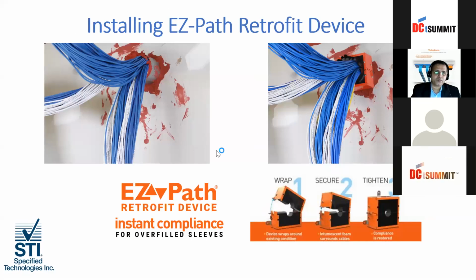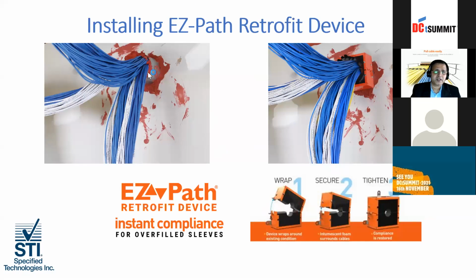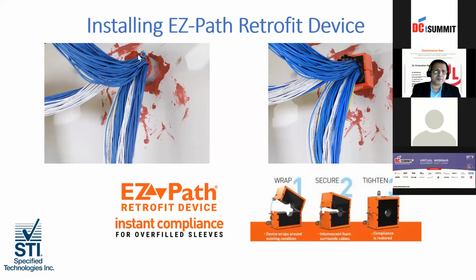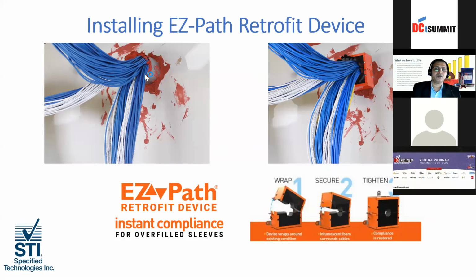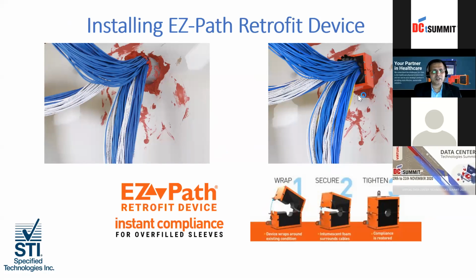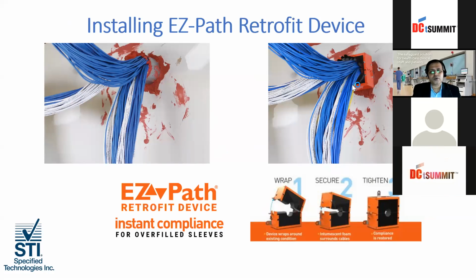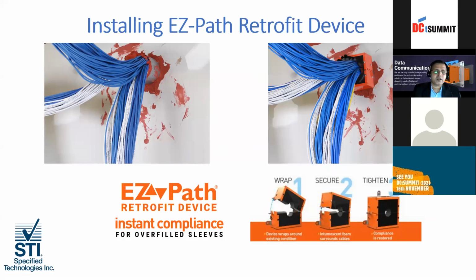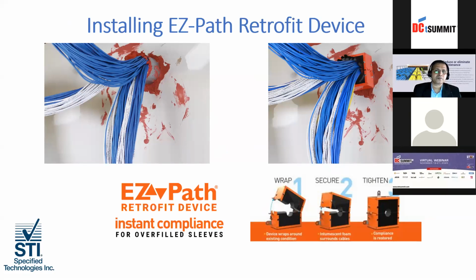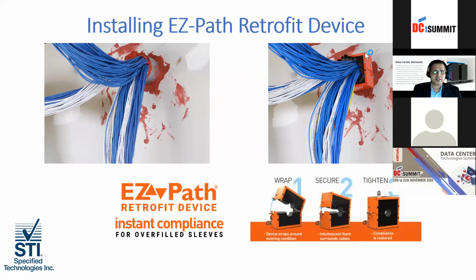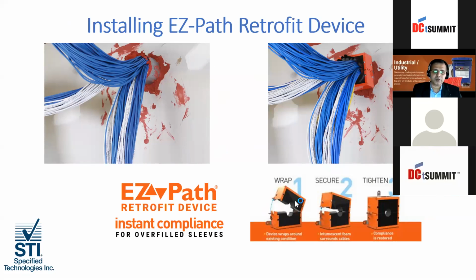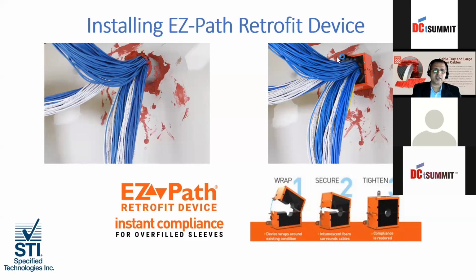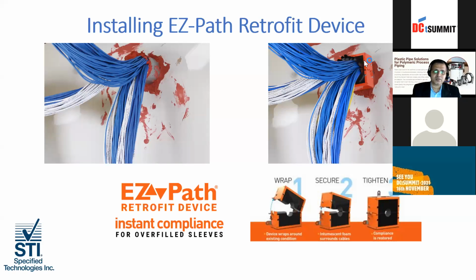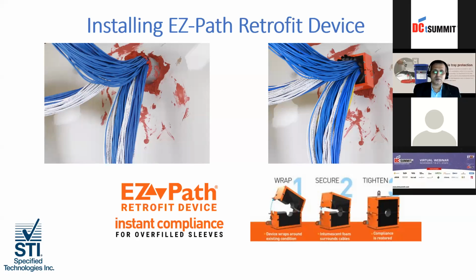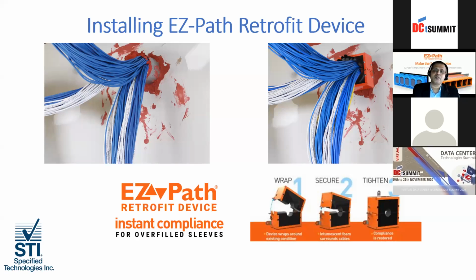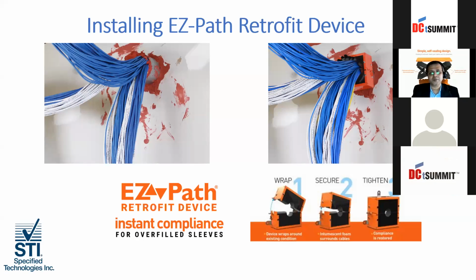This is an overfilled scenario, which you can see towards your left-hand side. The cables are 100% filled up, and the sealant is just applied for namesake. We have a retrofit device which is very easy to install, and it can support 100% filled cables, and the cables can be changed at any given point of time. The sleeve will remain as it is. The device has to be just, you can see at the right-hand side bottom, wrap, secure, tighten, that's it. And the cable can be pulled and pushed n number of times. The fire stopping device will remain as it is. So this is a retrofit. This can be used as a retrofit device where you have cables with almost 80 to 90% fill up.